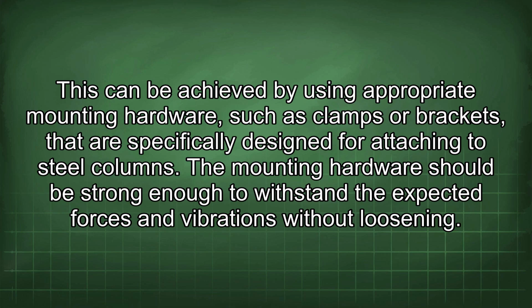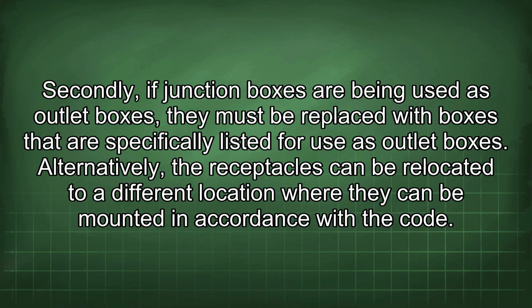The mounting hardware should be strong enough to withstand the expected forces and vibrations without loosening. Secondly, if junction boxes are being used as outlet boxes, they must be replaced with boxes that are specifically listed for use as outlet boxes. Alternatively, the receptacles can be relocated to a different location where they can be mounted in accordance with the code.